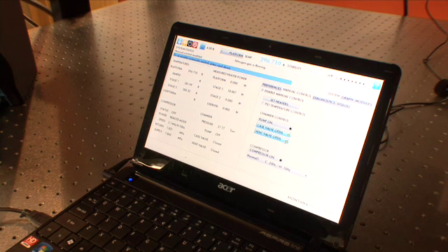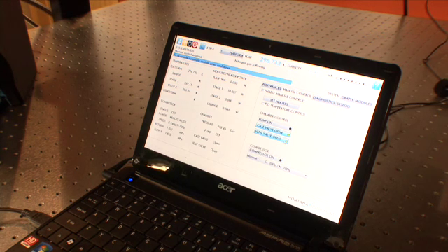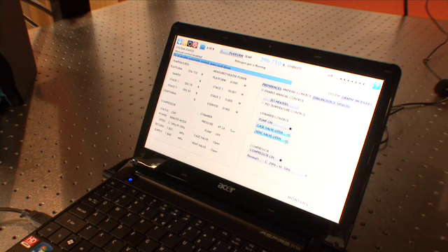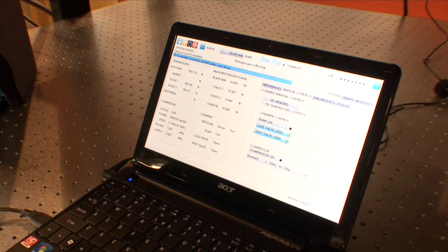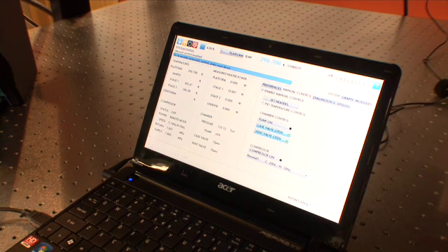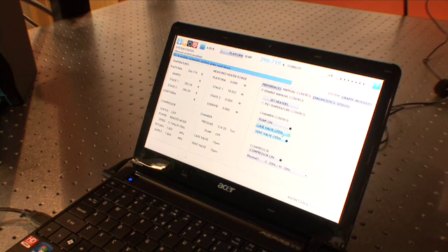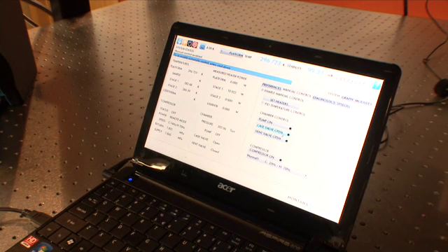You'll hear those click open and then the pressure will rise within the sample chamber. You only want to manually vent the system if your temperatures are all above 280 kelvin. You can press them off once you've reached room temperature and pressure.